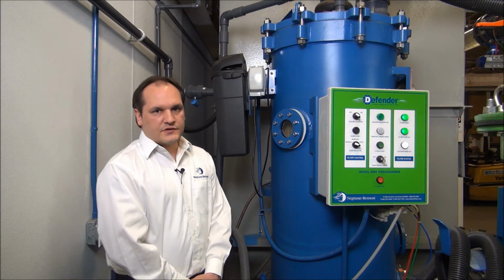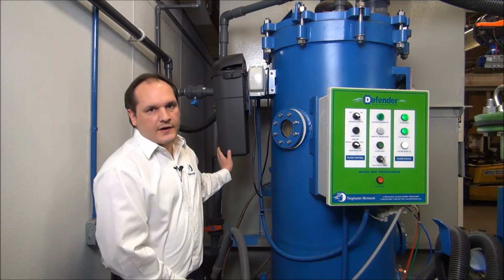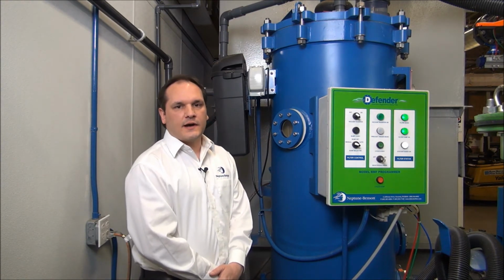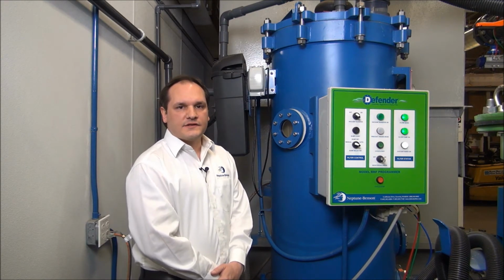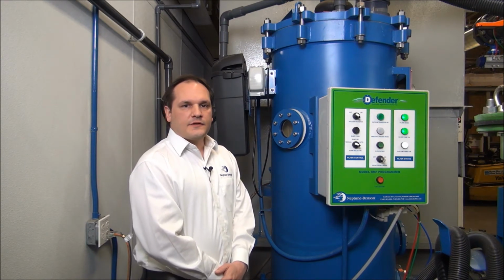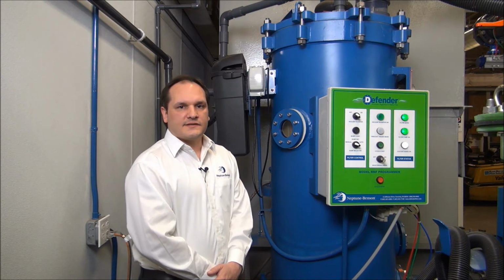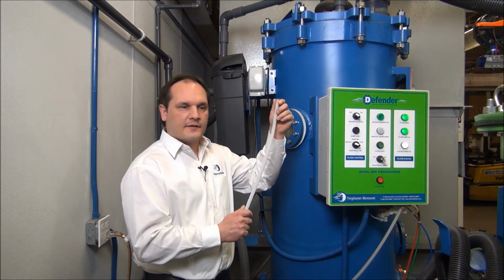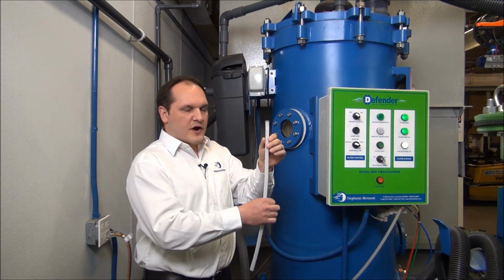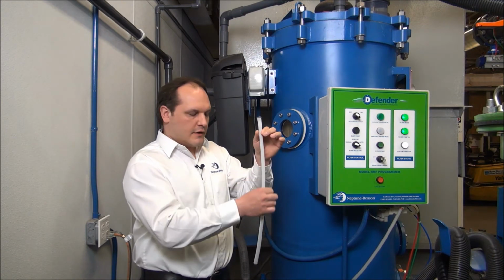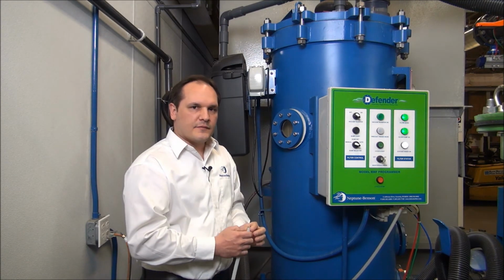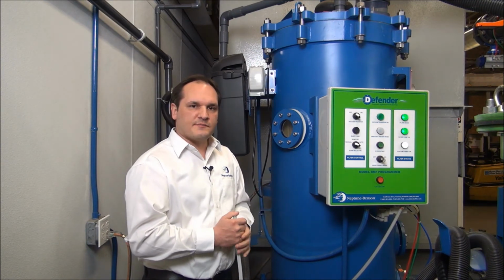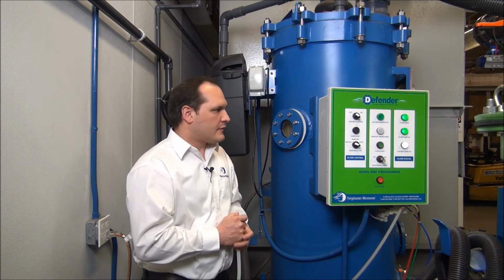The perlite media is introduced into the filter through a vacuum transfer in its dry form. After the media is loaded into the tank, the system is started up and the system automatically goes into a pre-coat process. Throughout this 10-minute pre-coat process, the media starts to build upon itself on the filter flex tubes which hang within the tank. Through this pre-coat process, we get a nice 1/8 of an inch coat of media coating on these elements. That's the filter medium. Perlite media is 85% open void space just waiting to collect dirt and debris.